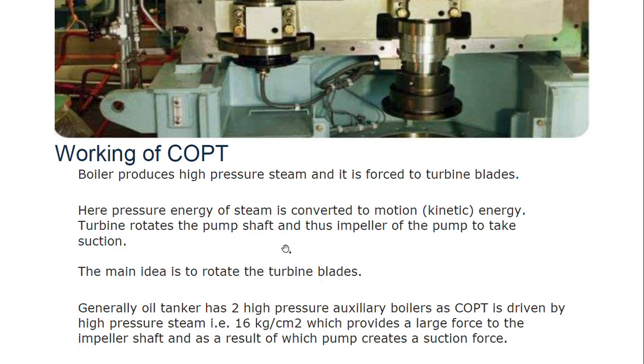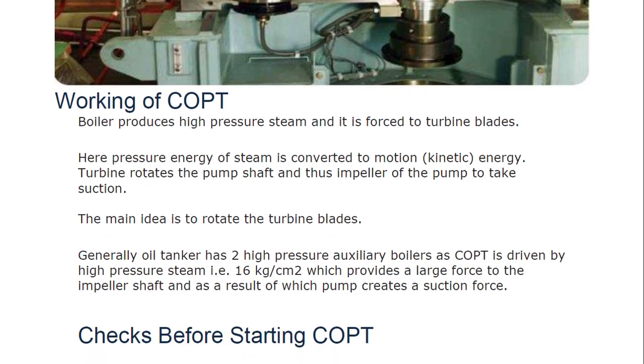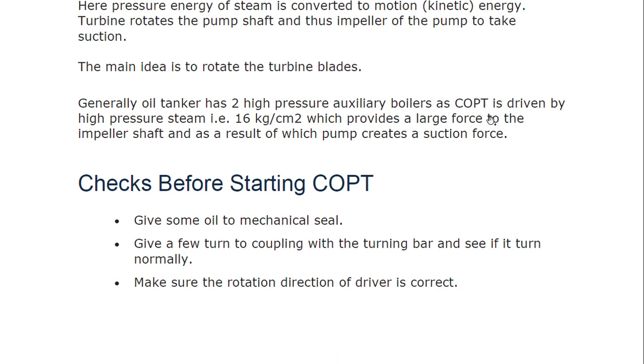The turbine rotates the pump shaft and thus the impeller of the pump to create suction. The sequence is: pressure energy converts to kinetic energy, the turbine rotates, the shaft rotates, the impeller rotates, which creates suction. The high pressure steam at 16 kg per centimeter square provides a large force to the impeller shaft, and as a result the pump creates a suction force.